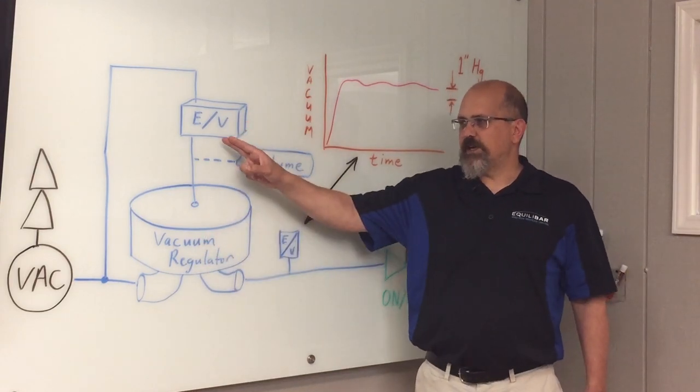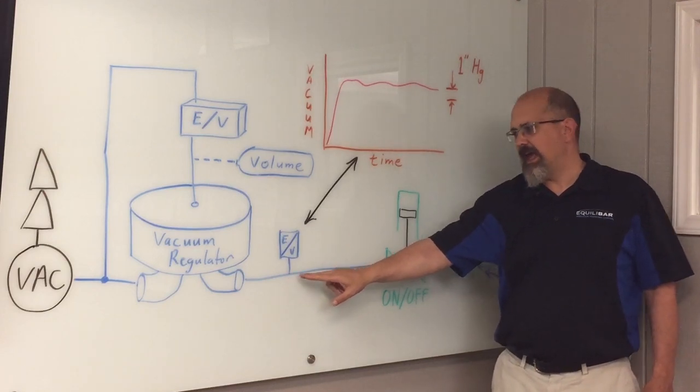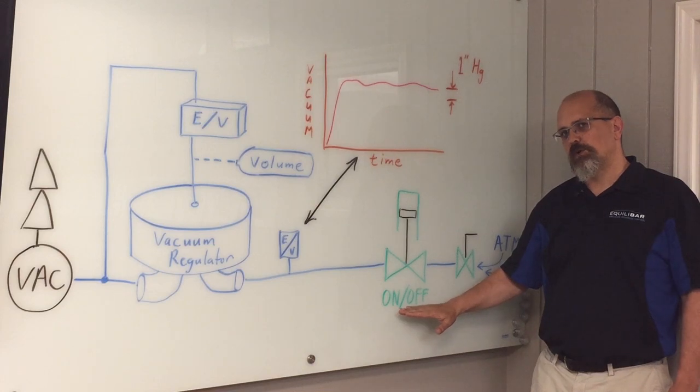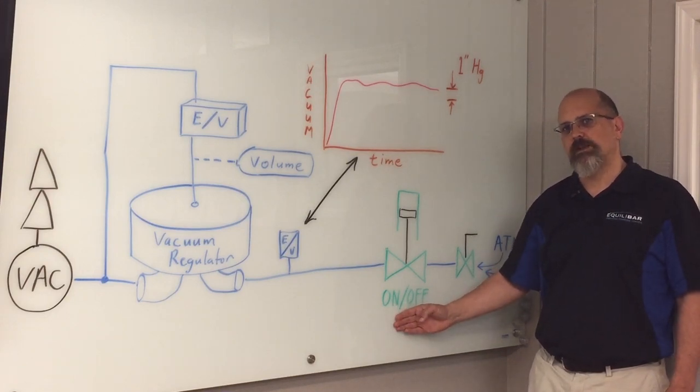We're going to set a fixed command. It's going to control a fixed vacuum pressure here, and what we're going to do is, with this on-off valve, we're going to put a flow disturbance into the system. Essentially, we're going to go from no flow to full flow with this on-off valve, and then back again.